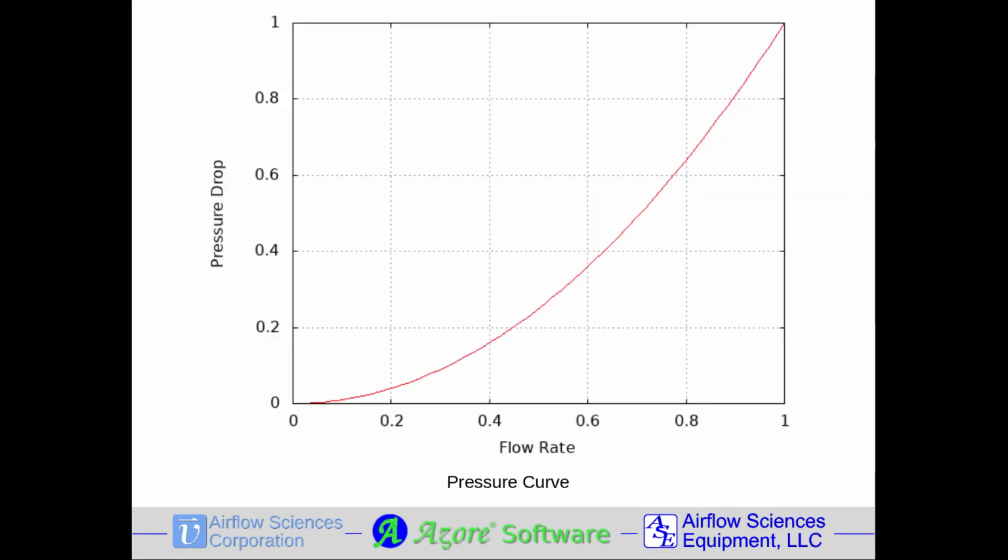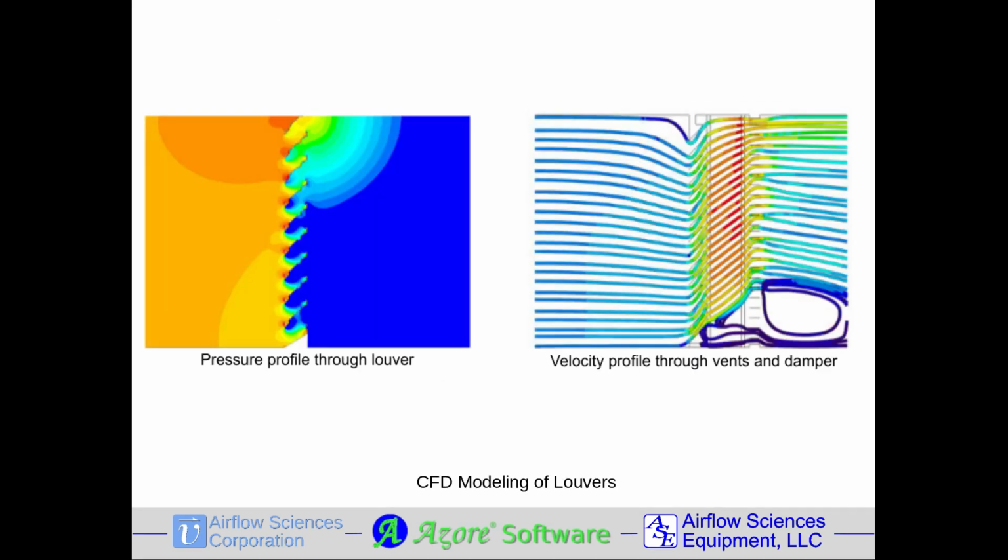Results include assessment at face velocities ranging from 300 to 1400 feet per minute, measuring flow volume, pressure drop, and throw. Architects and builders often require the pressure drop through an element for HVAC sizing calculations.